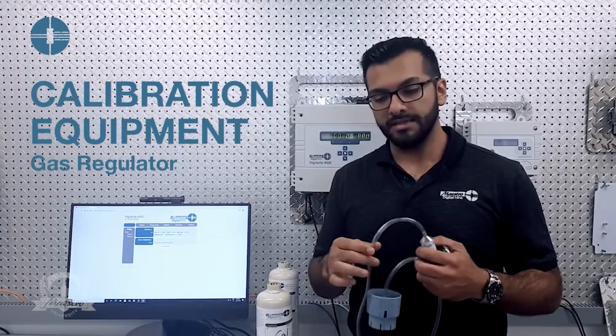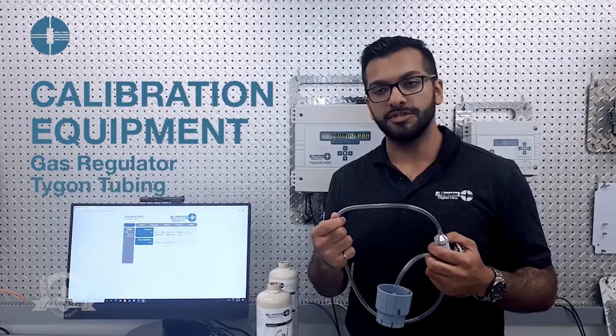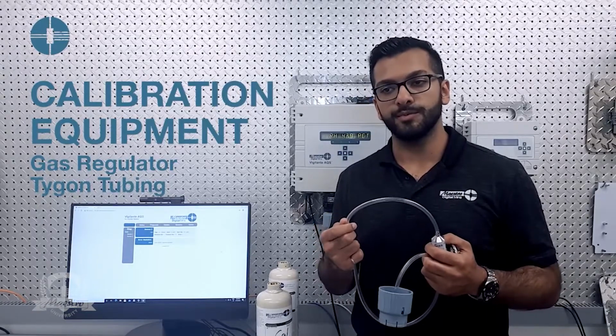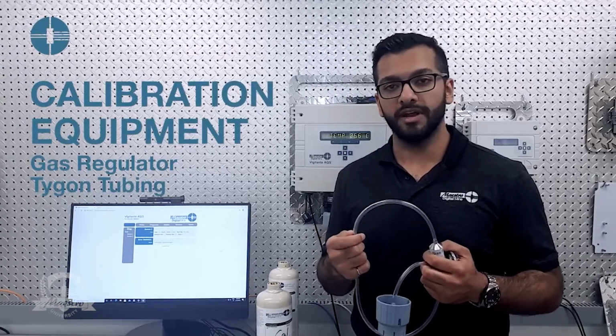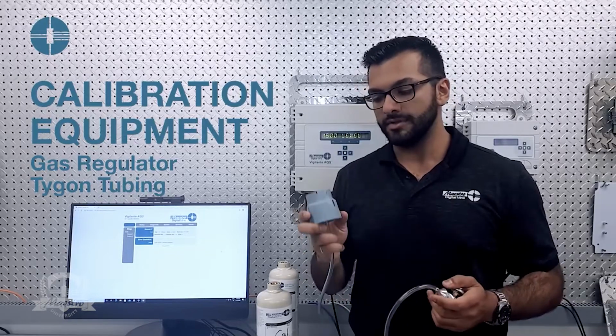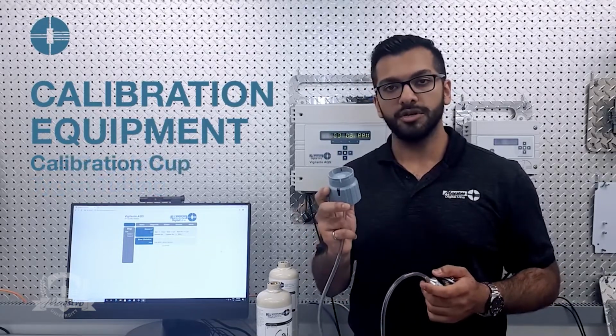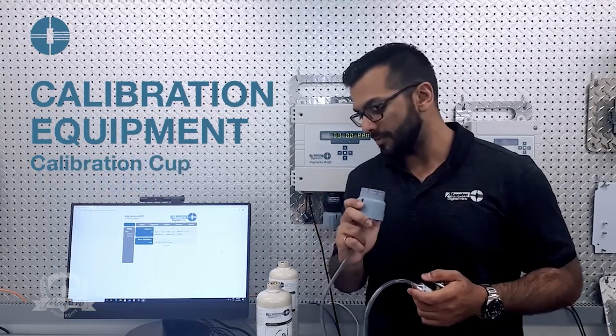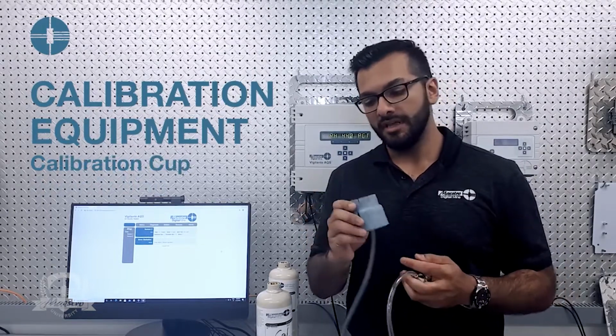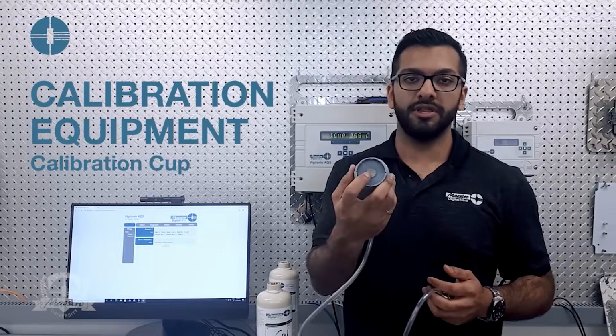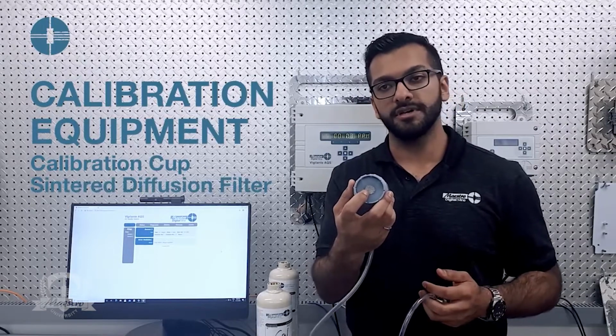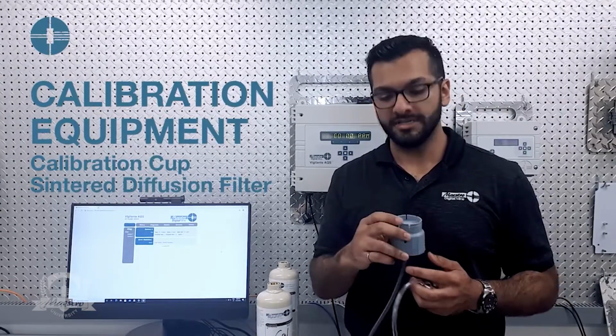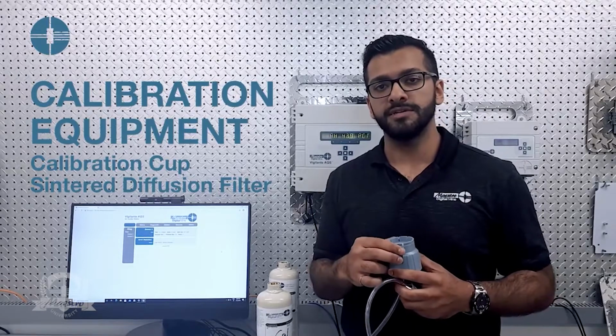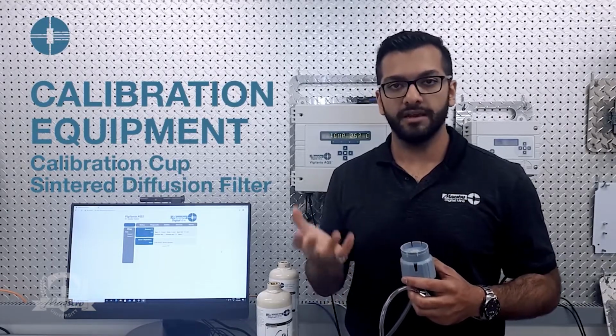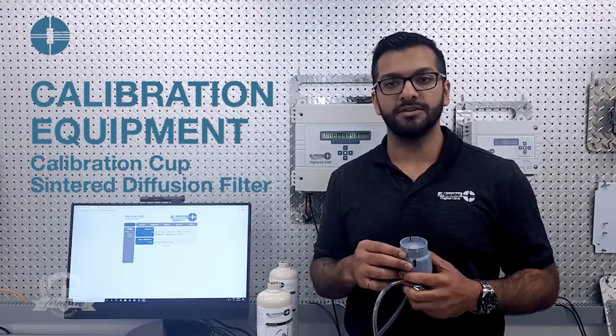The next thing is the Tygon tubing, which is a non-reactive tubing which we provide, used for calibration with all of our gas sensors. We also have, at the end of it, a calibration cup, which is used to supply the gas to the face of the sensor. The most important thing with this is to make sure that you have the sintered diffusion filter plugged in at the end. Otherwise, it's just going to force the gas into the sensor itself instead of letting it absorb into the sensor naturally as if it is in the environment.